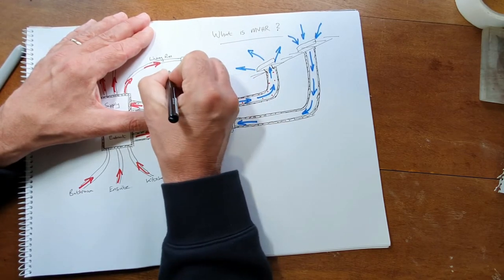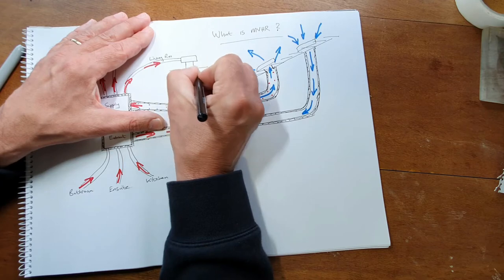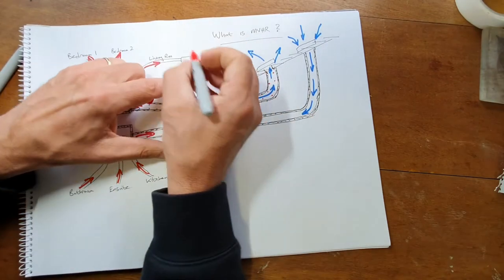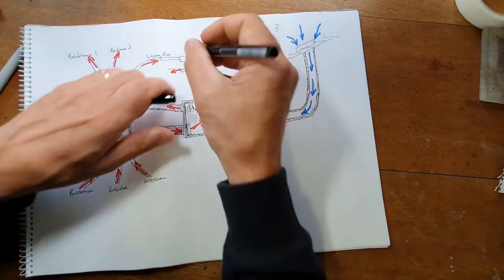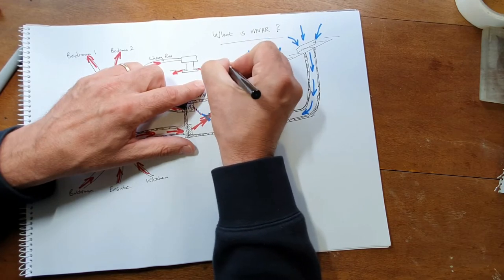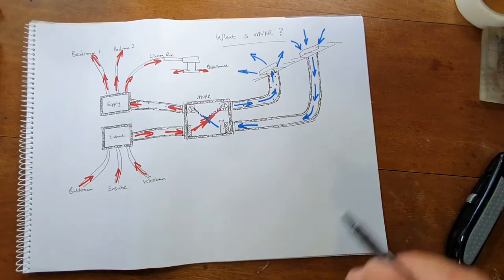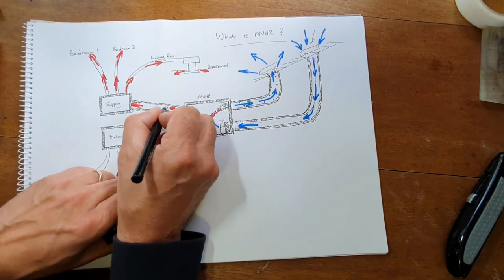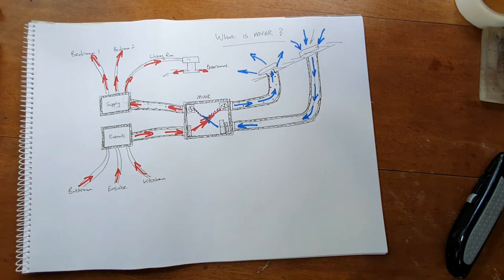Now I'll draw the ceiling plenum. This is the thing that you see in the ceiling when the whole system's finished. Hopefully you see it but you don't hear it. Pokes through the ceiling by about 20 millimeters so it's very low profile and quite nice looking you can paint them and they blend in very nicely look like a built-in speaker. So these ones the ones we use feed air out along the ceiling so it doesn't blow straight down onto the back of your neck when you're sitting in front of the TV gives you a stiff neck. So just to show you the flow of air coming in goes down that pipe through the heat recovery cell gets warmed up and gets fed gently into all your habitable rooms and then out of the plenums into your bedrooms.